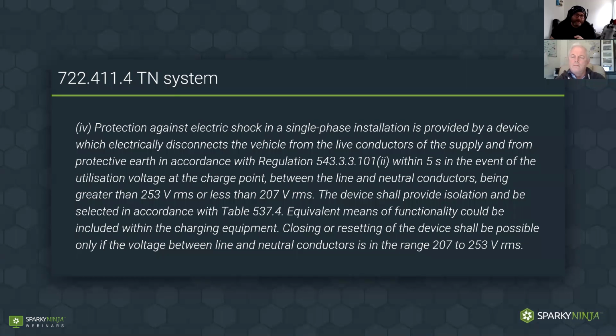Because if this was for three-phase installations, you could actually have a varying demand on other phases. And what that could mean is I could have so much demand on one phase that the neutral actually is no longer in the center where you think it would be. And so when you have an open PEN, the actual neutral has shifted over, and whilst the loads are pulling on one of the phases, maybe the phase that your electric vehicle charging point is connected to, the voltage might stay in that window of 207 to 253, whilst another one might go up over to 300 volts or go down below 100 volts. You know, it's proportional to the demands of the other phases.